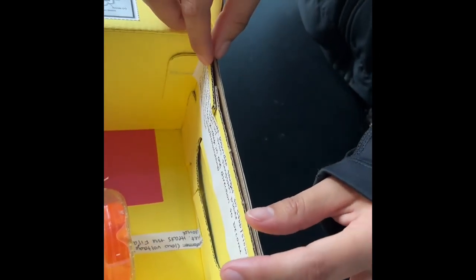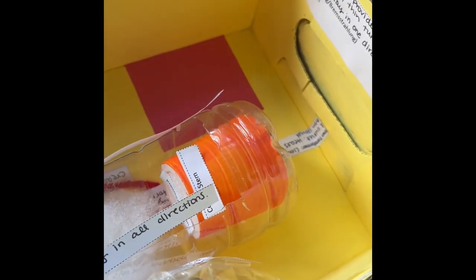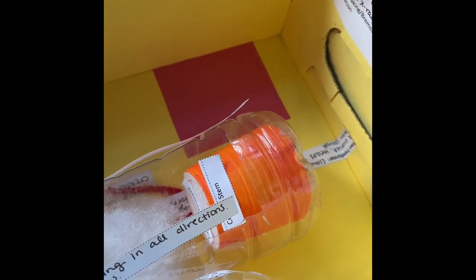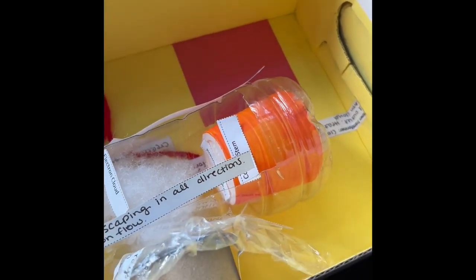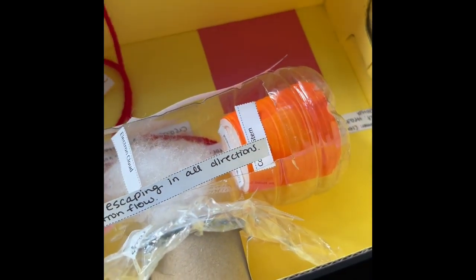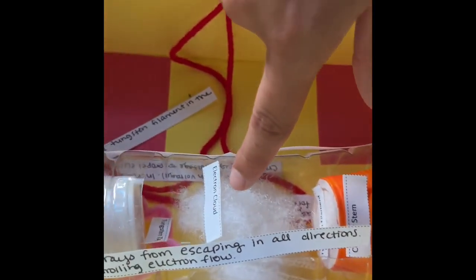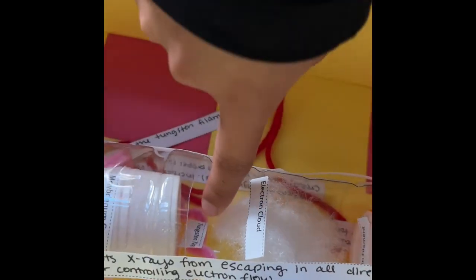Next, we got the anode, which is right here. The component is known as the positive electrode, and it provides a target to stop the flow of high energy velocity electrons, and consists of the copper bar with the thin tungsten plate, and it's embedded in the face of the focusing cup of the cathode. And then the last 2 we have here are the electron cloud and the tungsten target.